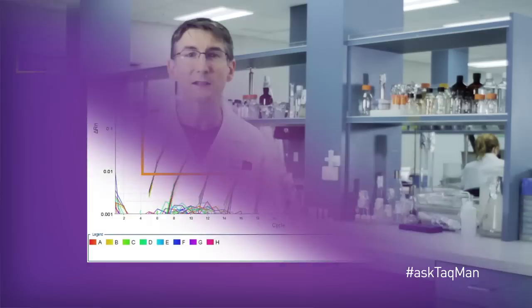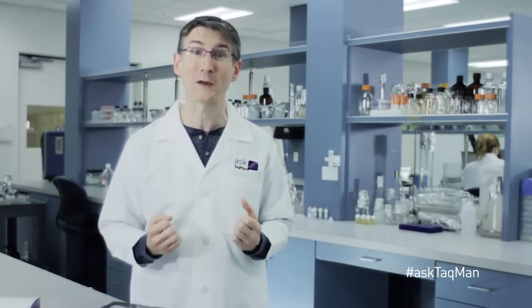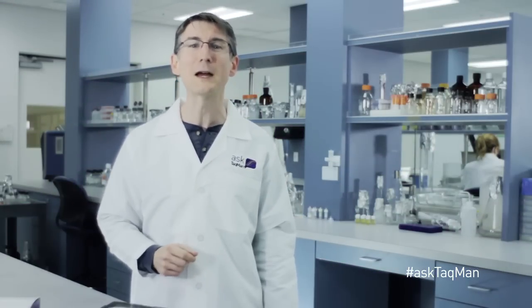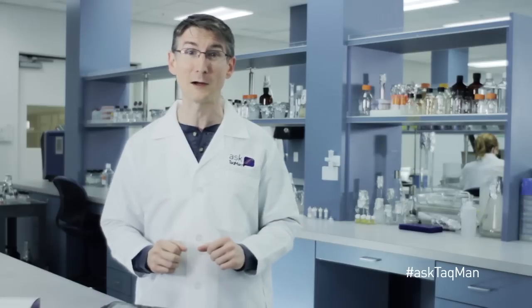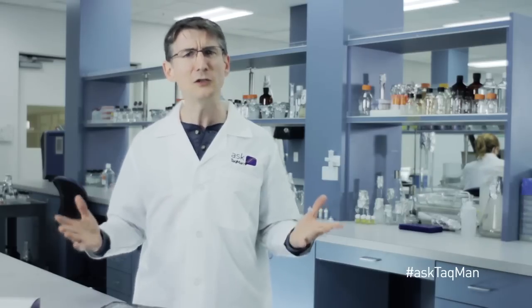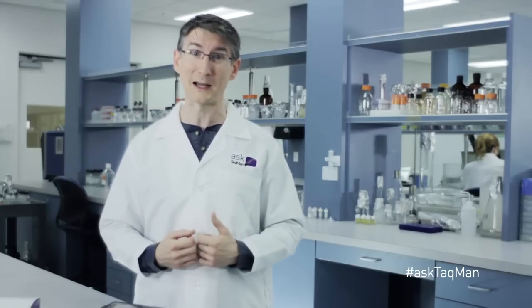The point is, we always want to look at our data in the geometric phase, since this is where we'll get the best results, especially for a quantitative reaction. Now, how do we do that? Well, by making sure that that's where the threshold is set. And if you want to know more about thresholds, please watch our other Ask TaqMan video on setting these properly.